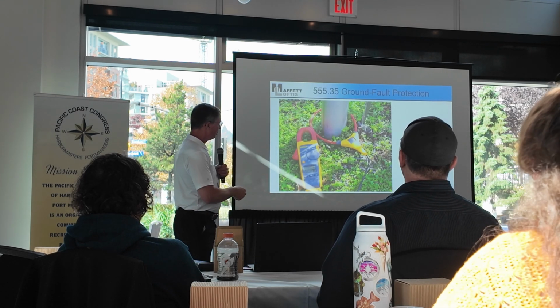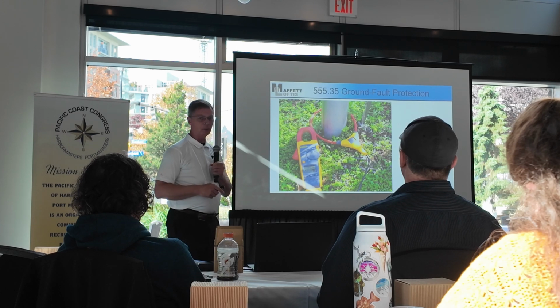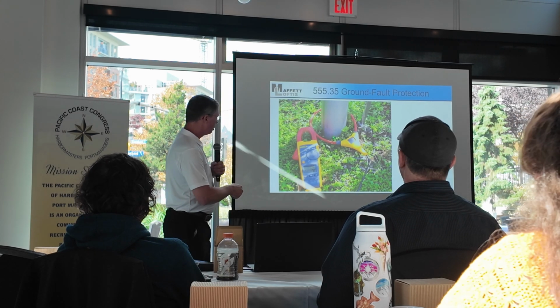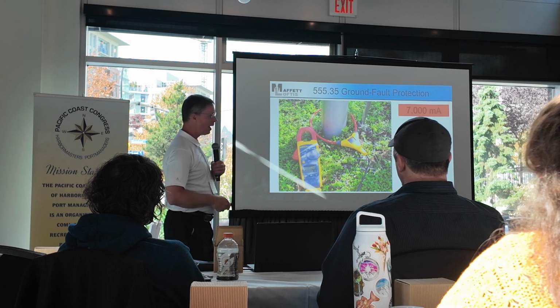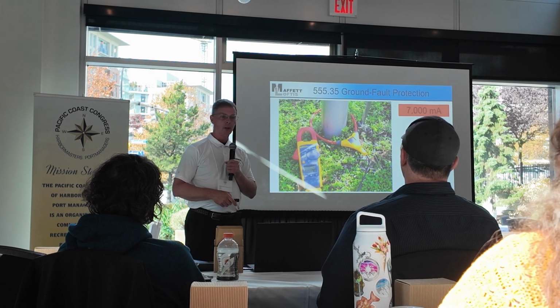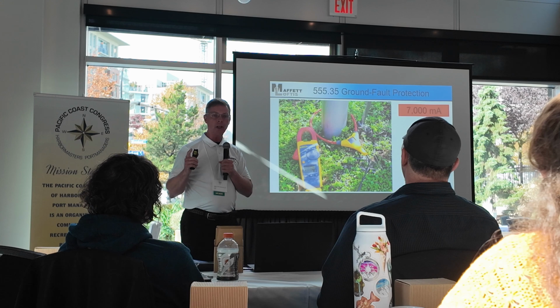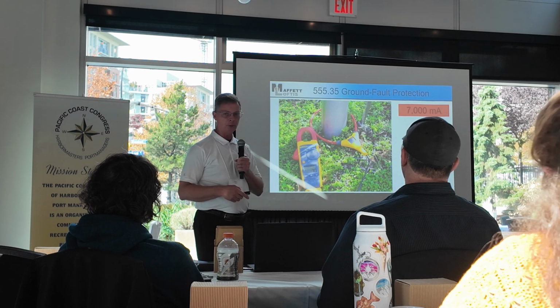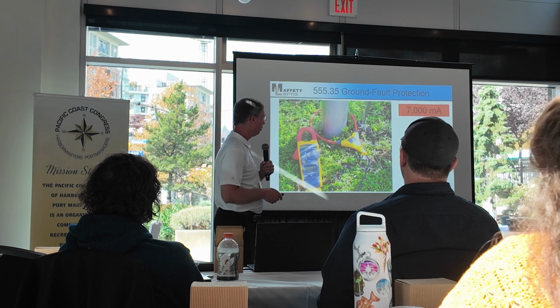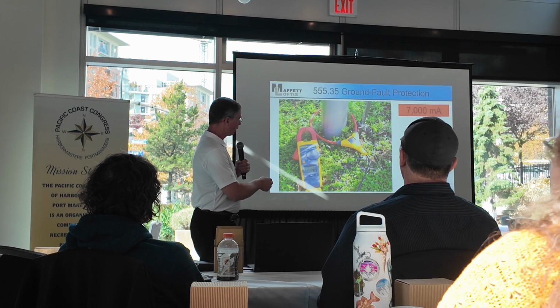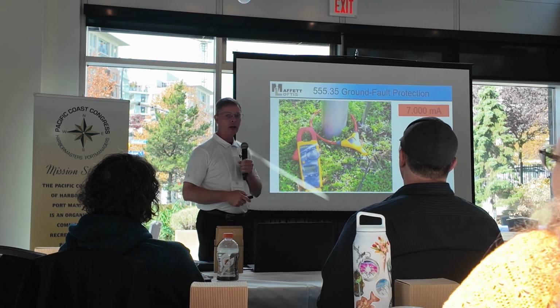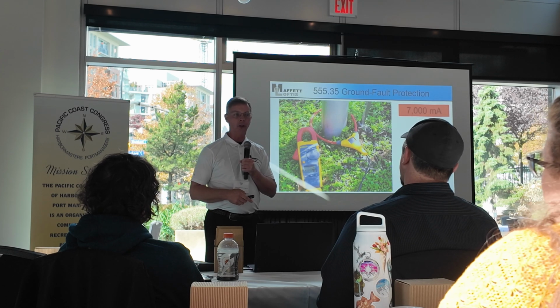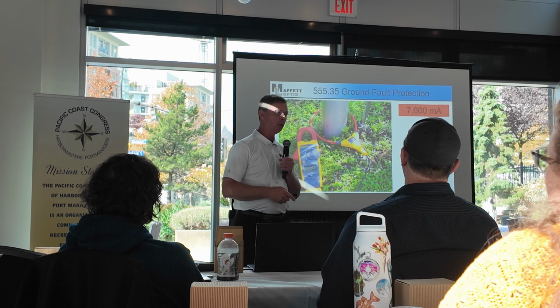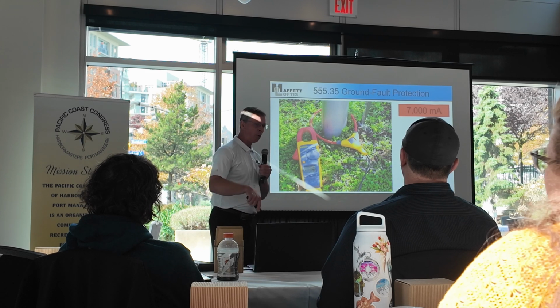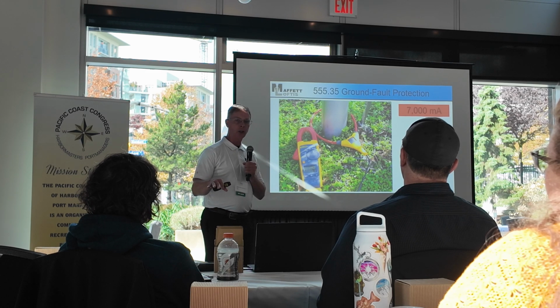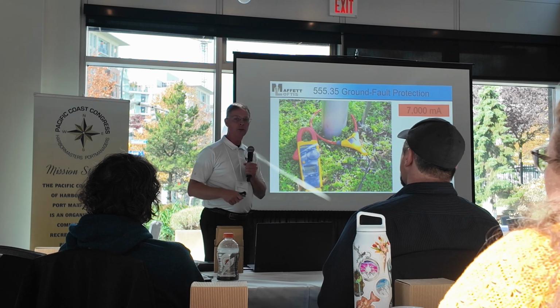Okay? And one reason is, I want to talk about ground fault and understanding it. This right here is measuring leakage current up to 7,000 milliamps on this one surface. Okay, 7,000 milliamps, because every electron will make its way back to the point of return. I actually clamped the ground rod, and that ground rod had right at 7,000 milliamps of return leakage current on the grounded system. So it's really incredible. And that's one reason why we want surfaces close to the body of water to have this equal potential plane, so it's safer.